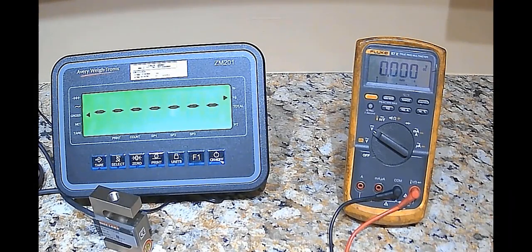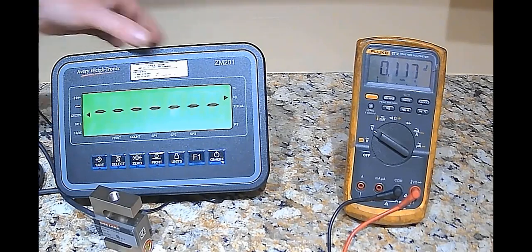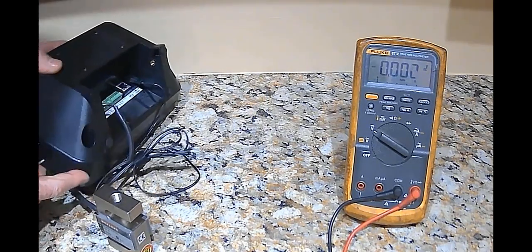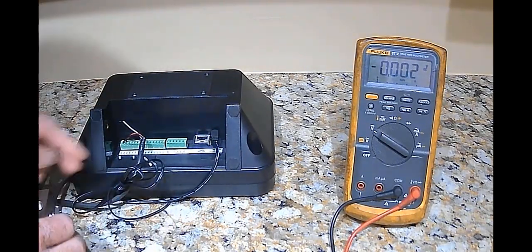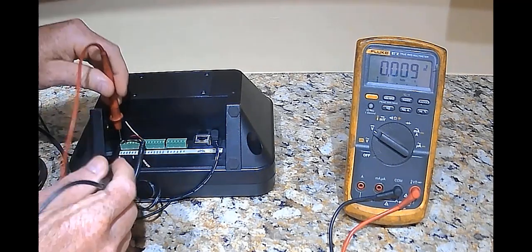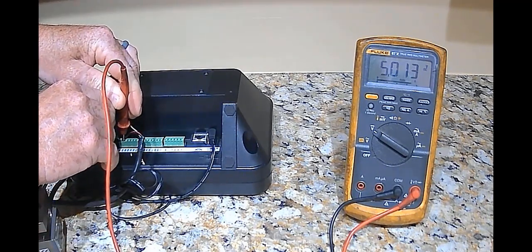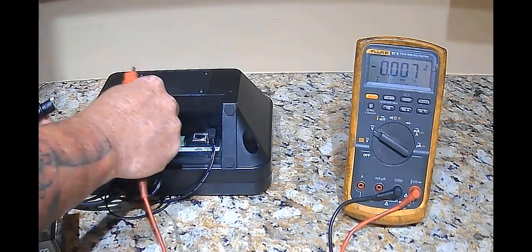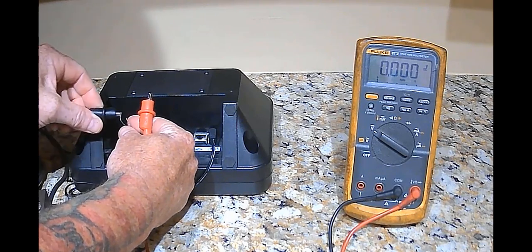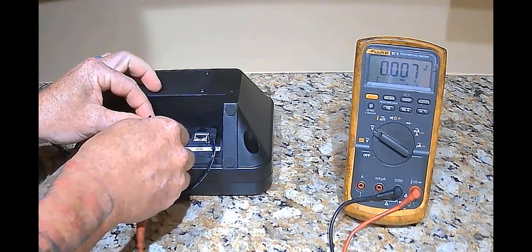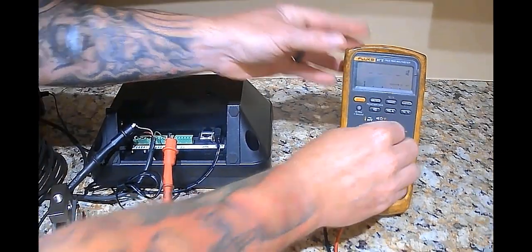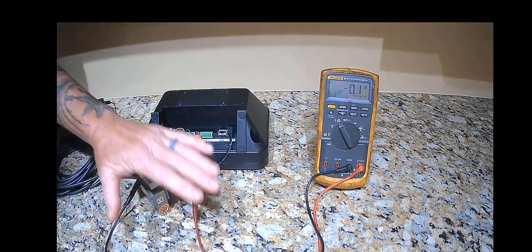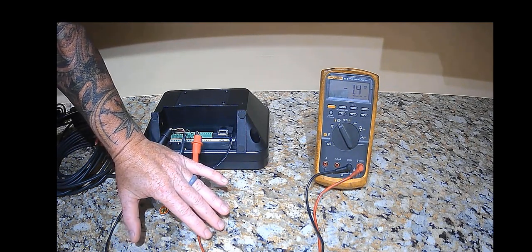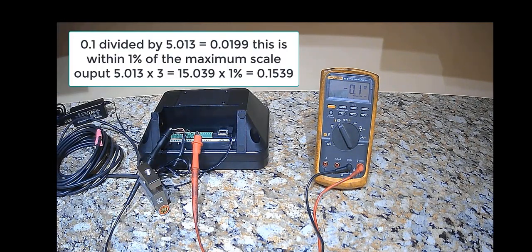All the weight, including the dead load, has to be removed from the load cells. With the cells powered up, measure the excitation voltage and write it down. Next, measure the millivolt output. Always add a force to the cell to make sure it is active. Record the zero balance reading. The common value for zero balance shift is 1% of maximum scale output.